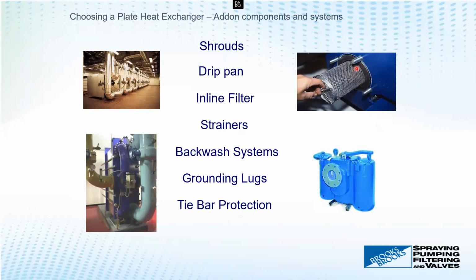If this was on the end connection on the header, how would we get the piping off to get the basket in and out? So it comes out the backside, but that's something that has to be decided way before you order the heat exchanger. If that's not something you're interested in doing, you can do outside pre-filtering.